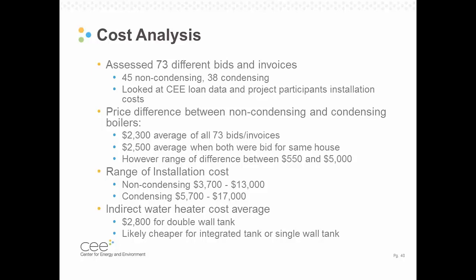And then the indirect water heater costs averaged right around $2,800 with a very tight range. I would say anywhere from like $2,700 to about $3,000. So it likely would be cheaper if you had an indirect or an integrated tank, as in some of the combi boilers, as well as the single wall tank that Ben was talking about. We just didn't have any in our studies.